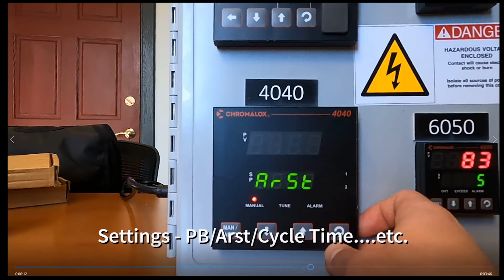your window now becomes the concern. If the window's too tight, it doesn't have enough information to understand. It might overreact or underreact. If it's too long, it may take too long to react. A lot of times I find that the auto reset is usually set too small, because then it starts taking small bite-sized pieces of the process, right? We're getting to temperature, we're not getting to temperature. And if it's really short, you might be almost to temperature and it shoots at 100% and you don't want it to. So if you increase that time that it has to calculate its PID, it helps a lot of times.